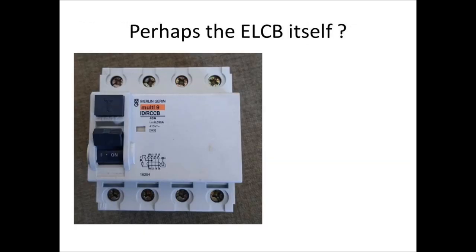Lastly, if it seems inconclusive — that is, no single appliance is consistently causing the tripping — then it could be the ELCB itself. This can be the case if the ELCB is very old and needs replacement.